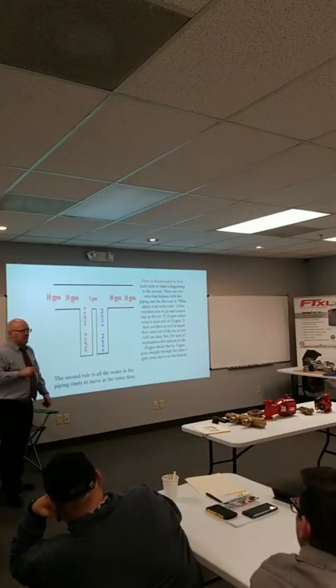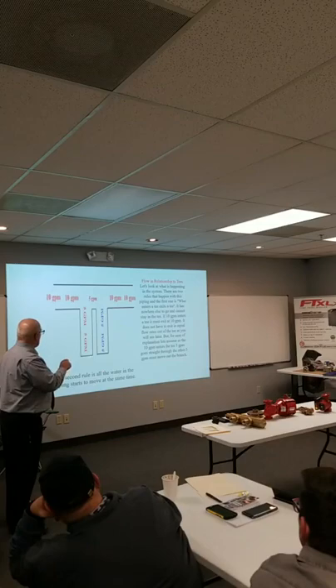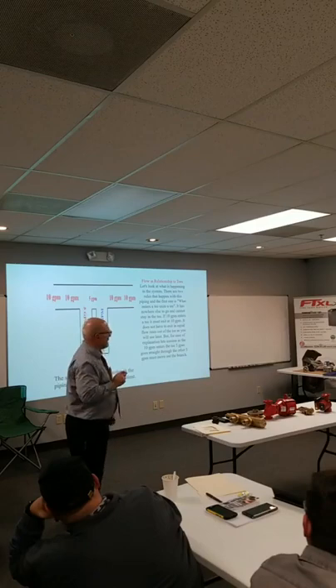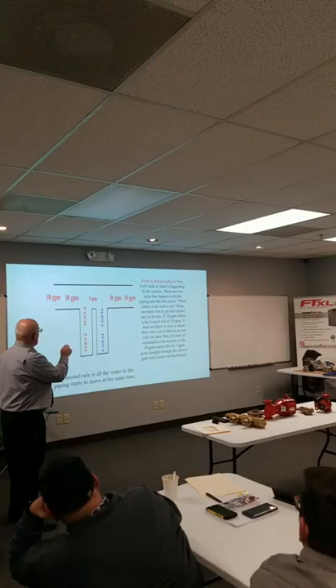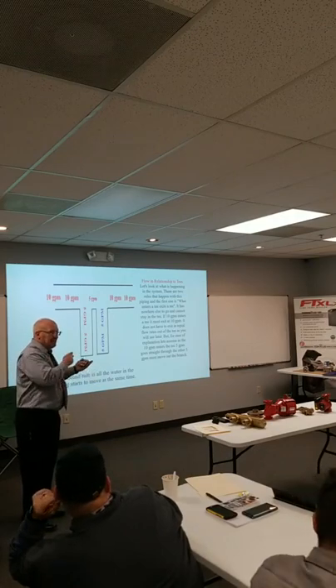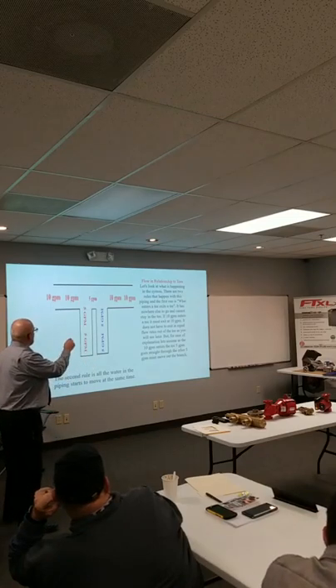As soon as I turn that boiler pump on, the secondary boiler pump, it needs 5 gallons a minute. So it takes 5 gallons a minute, pumps it through the boiler, puts 5 gallons a minute back. And let me tell you, one of the principles of primary secondary tees is that what goes into a tee must come out of the tee. It's a very simple process. So if I take 10 here, I take 5 out, I put 5 in, I got 10 coming out. What's between the tees? 5 gallons a minute, like it says. This side's easy because I put the number there. So it's easy. But 10 gallons a minute, 5's going through the tee.